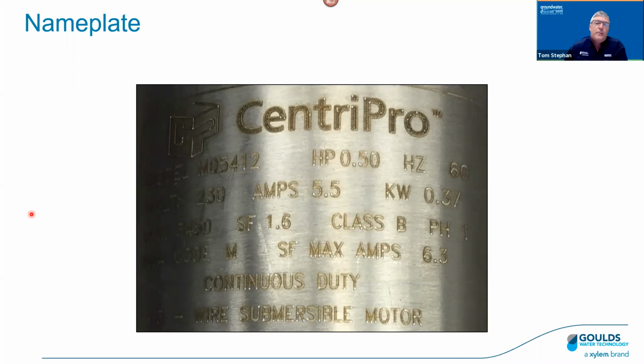Let's start with the submersible pump nameplate. So as we can see here, we have an M05412, that's the model or the part number, and that's motor. 05 is half horsepower, 4 is 4-inch, 1 is a 3-wire motor with a ground, and the 2 is a 230-volt motor. Moving across here, we can see that's a half horsepower, 60 hertz motor, 230 volt. Amperage here is 5.5 amps. So sometimes we see FLA or full load amps. In this case here, we're just showing amps. So basically they're the same, full load amps, amps.